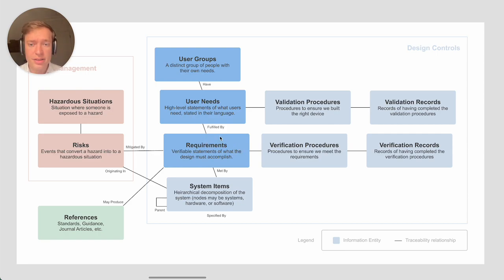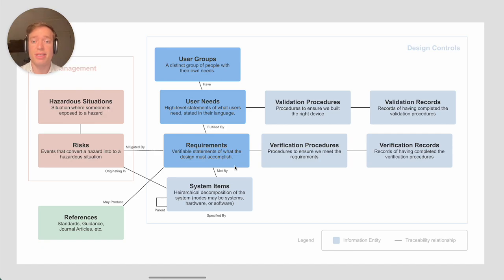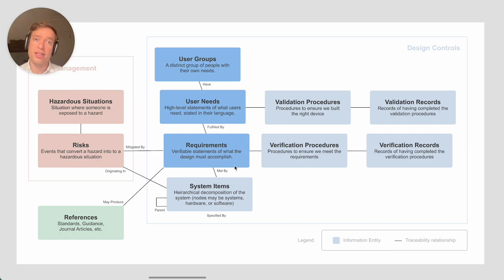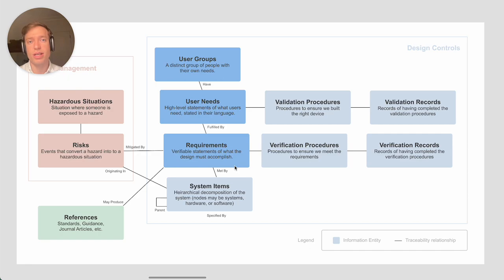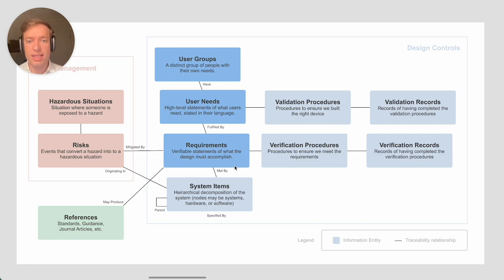Then we've got requirements. Requirements are different than user needs in that they need to be verifiable. You need to be able to write a procedure, perhaps a unit test or some sort of inspection or end-to-end test that could ensure that that requirement is met.